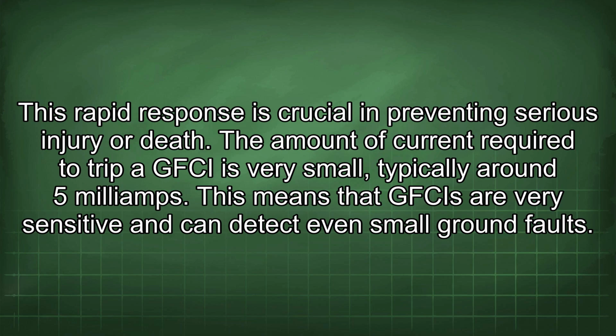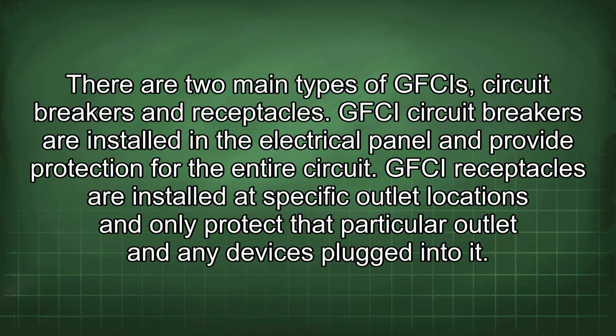The amount of current required to trip a GFCI is very small, typically around 5 milliamps. This means that GFCIs are very sensitive and can detect even small ground faults. There are two main types of GFCIs: circuit breakers and receptacles. GFCI circuit breakers are installed in the electrical panel and provide protection for the entire circuit. GFCI receptacles are installed at specific outlet locations and only protect that particular outlet and any devices plugged into it.